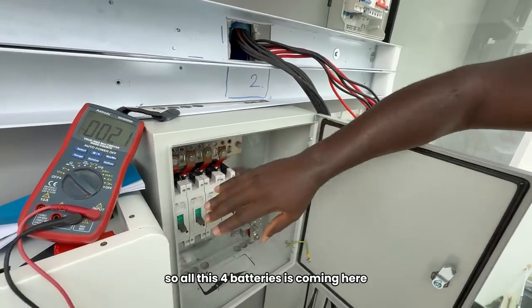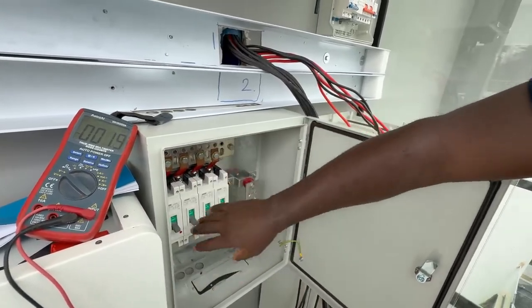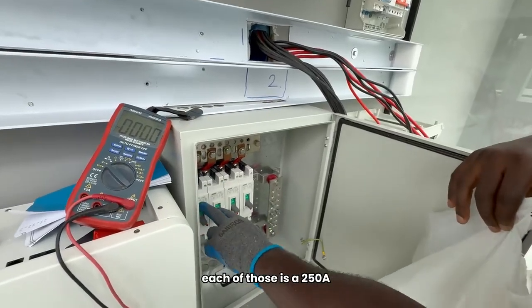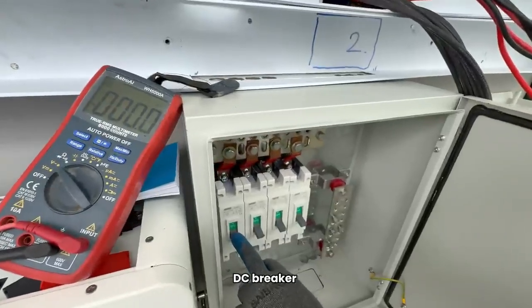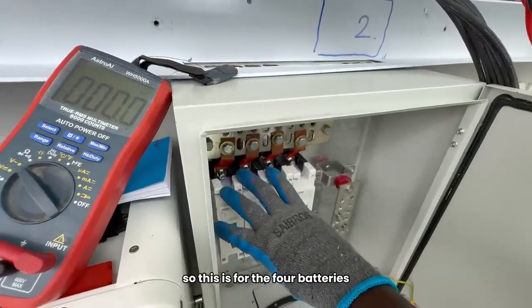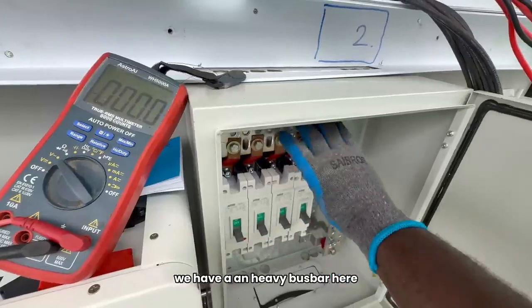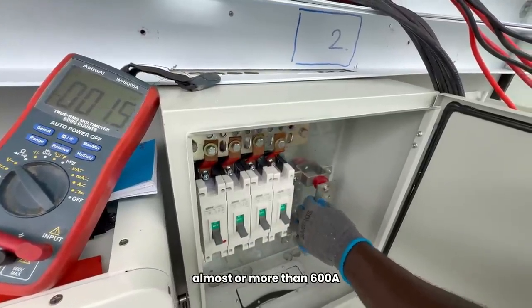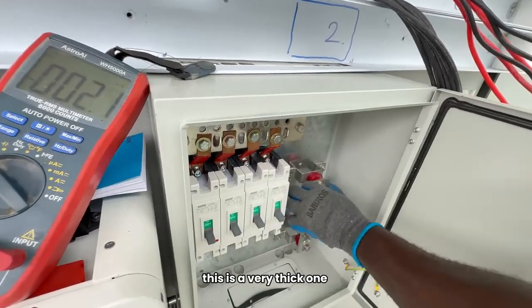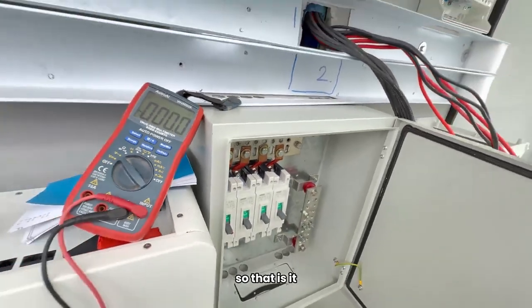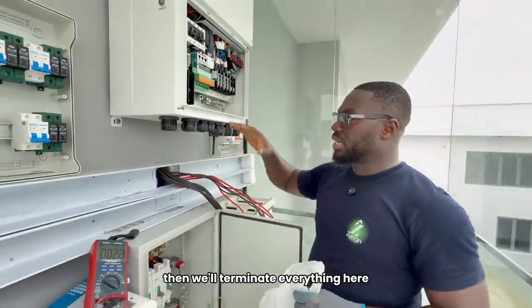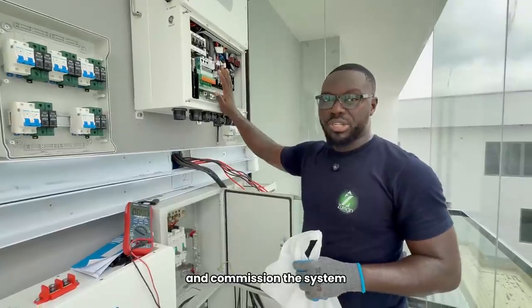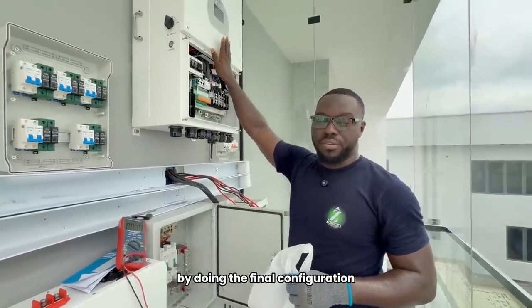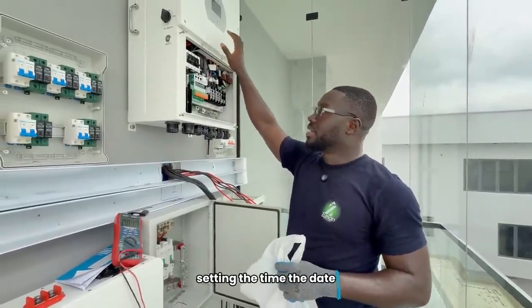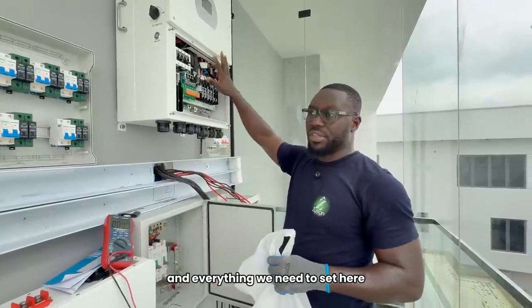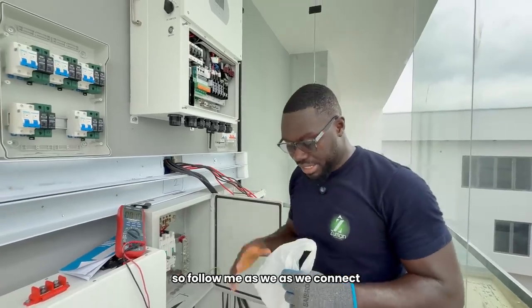This is your battery bus bar. So all those 4 batteries are coming here. Each of those is a 250 amps breaker, DC breaker, 250, 250. So this is for the 4 batteries. We have a heavy bus bar here, more than 600 amps. This is a very thick one. So that is it. So in no time, we'll be doing all those connections. Then we'll terminate everything here and commission the system by doing the final configuration, setting the time, the date, the battery charging, and everything we need to set here. So follow me as we connect.